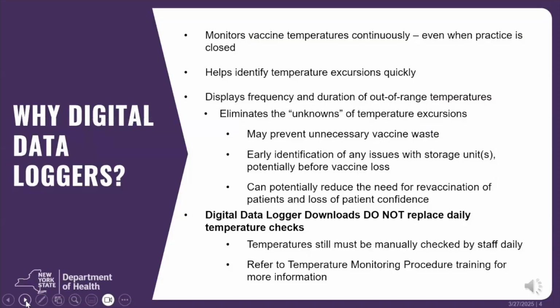There are a number of reasons why digital data loggers are a useful tool for VFC providers. Downloaded and saved logs can indicate how often and for how long temperatures may have been out of range. Vaccine manufacturers use this data to determine whether the vaccine is still viable. In cases such as power outages where temperatures would have otherwise been unknown, vaccine can be saved from being discarded, or possibly reduce the likelihood of revaccination if action is taken quickly enough.